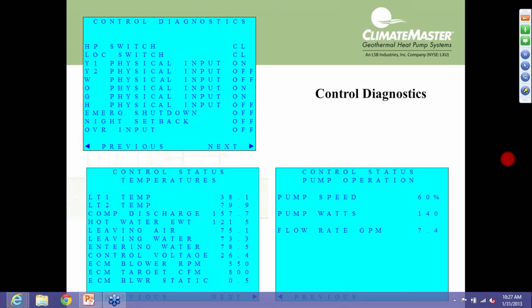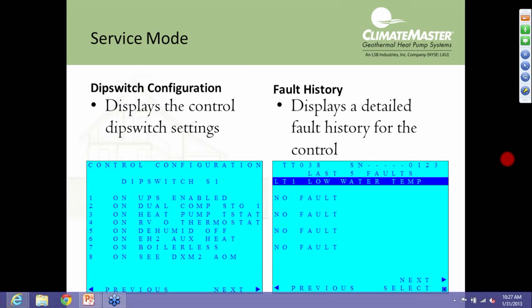The next thing under service mode is our dip switch positions. Now you cannot change the position of the dip switch here electronically, but you can at least see what position they're in, and it gives you a brief description of what that dip switch is. So earlier today, I mentioned on dip switch bank 1, number 2 is for that dual compressor unit. So again, that should always be in the on position.